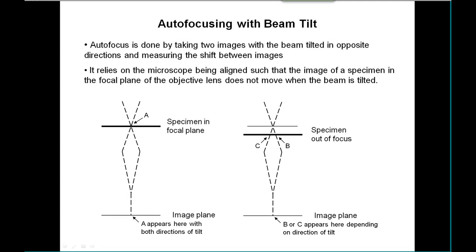Now let's talk about focusing. Auto-focusing is done using an old standard technique of taking two images with the beam tilted in opposite directions and measuring the shift between the images. If the specimen is in the focal plane, a point on the specimen appears at the same place in the image with both directions of tilt. But if we're out of the focal plane, the tilted beam projects to a different image point in the two conditions of tilt, meaning we get a shifted image in the two cases.